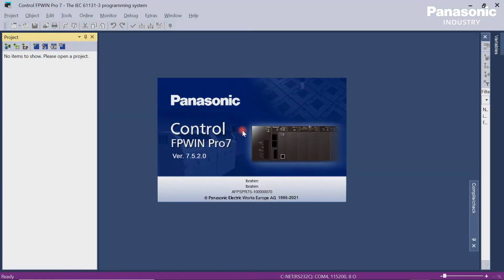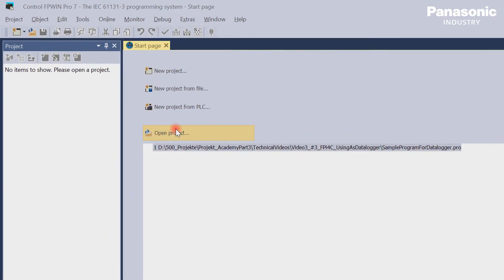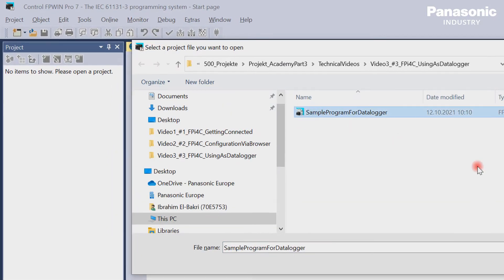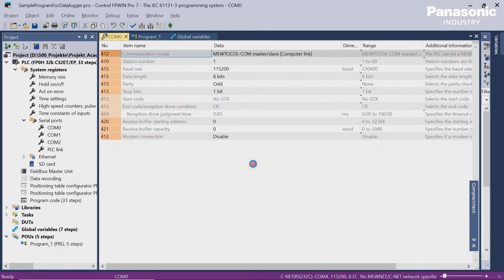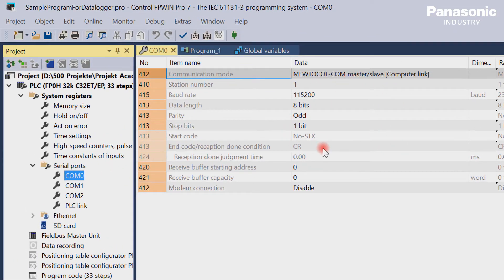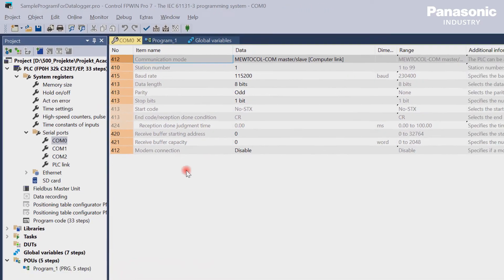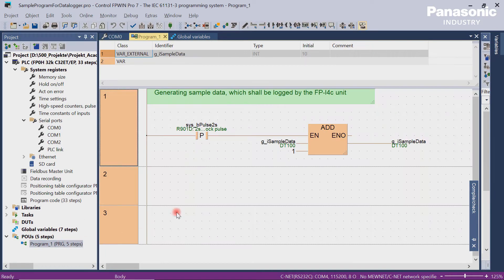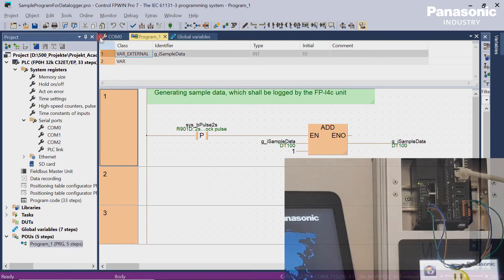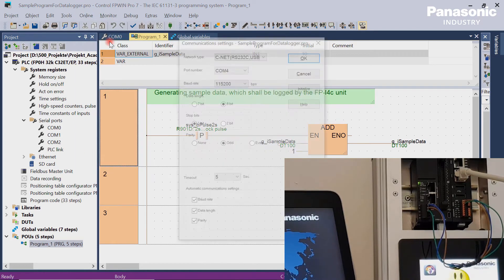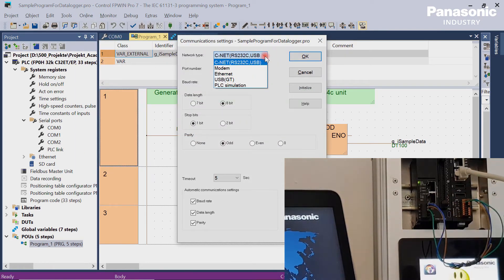The second step is to open our FPWinPro7 programming software in order to set the configuration parameters for the COM0 port on the PLC side. Be aware that these configuration settings for the COM0 port must be equal to the settings in the FPI4C unit later on. We also create a sample program that generates some sample data, which we want to log by our FPI4C unit later on. After all the changes are done, we download our program into our PLC.